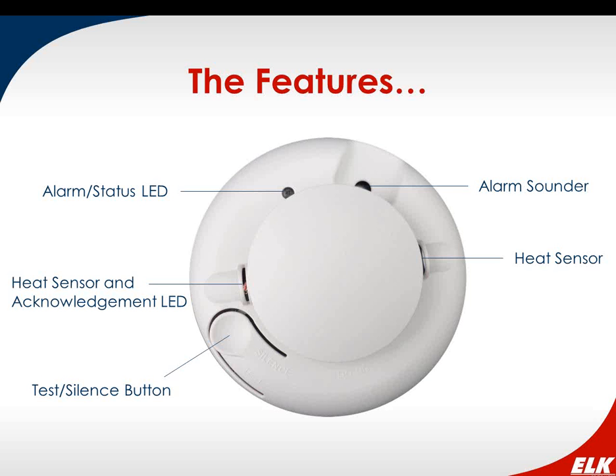The alarm status LED is clearly visible when you look up at the smoke detector. There's a nice little lens there that amplifies that LED and allows you to really see it when it's lit up. During normal operation, that LED is going to blink about once every 16 seconds or so. So it's just a little heartbeat there to let you know that it's alive and doing what it needs to do.